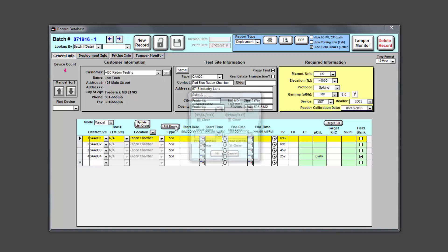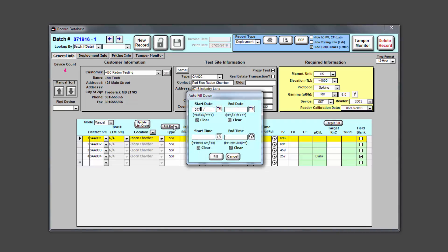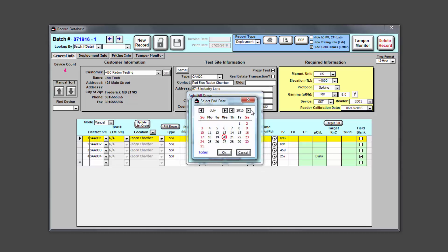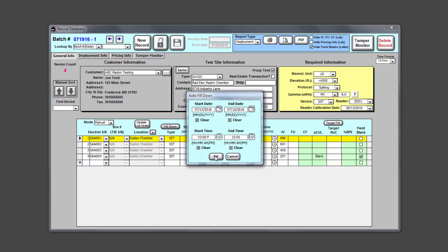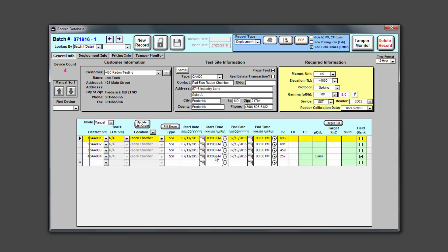Note that the dates and times of the exposure will be located near the bottom left-hand corner of the spiking service form that you received back in the mail from Radelec. You can either type in the dates and times using the keyboard, or click on the calendar or clock buttons in either a 12 or 24 hour format. After we've finished entering in our exposure dates, we can begin to fill in the final voltages. You're going to need to read the electrets using your own SPER-1 voltage reader. Read them three times each, ensuring that you get the same voltage with each pull. If you're oscillating between two numbers, like between 515 and 516, keep reading until you get three identical numbers in a row. As we enter in each final voltage, the radon concentration for the corresponding electret is being calculated — except for the shipping blank, which was hopefully not inadvertently exposed to the radon chamber.